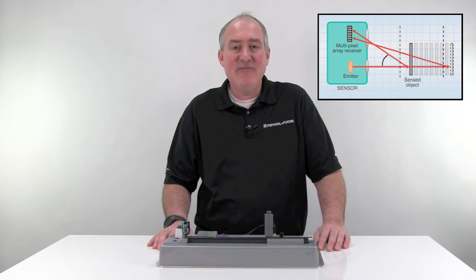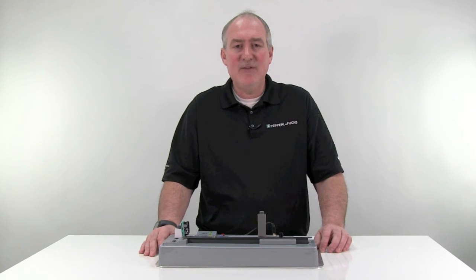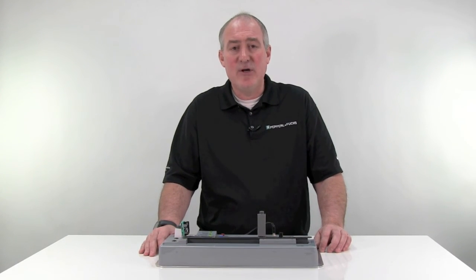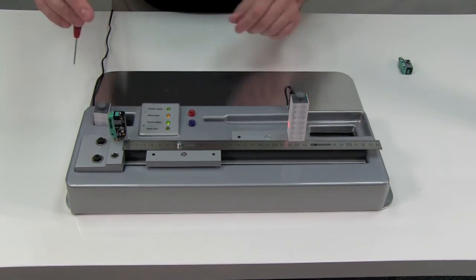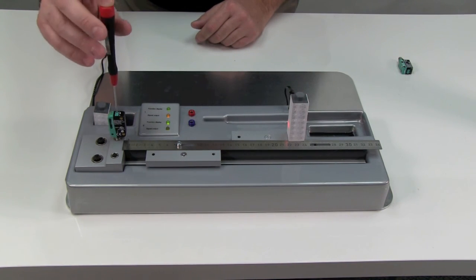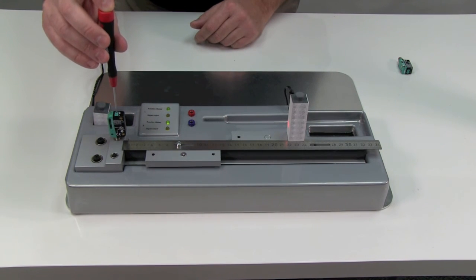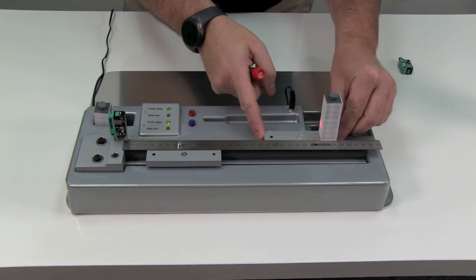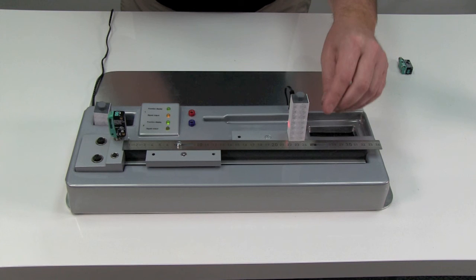Unlike diffuse sensors, background suppression sensors have a sharp cutoff, allowing them to detect targets in the foreground and suppress objects beyond a set distance. Now let's do the demonstration again, this time with the R100 background suppression sensor. Like I did with the diffuse sensor, I'll adjust the R100 so that it just sees a white target at 200mm. I'll turn the potentiometer counterclockwise so the output just turns off, then slowly turn it clockwise until the output just turns back on. As I slide the white target out of range and back into range, notice how the R100's output turns on at precisely 200mm, unlike the diffuse sensor which turned on around the 220mm range.